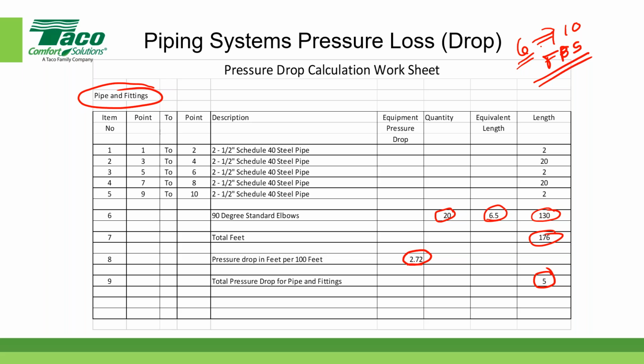Now, in our case, we said less than 8 feet per second. So the larger you make the pipe, the lower the velocity, and the more risk you have of collecting air and not moving the air along and removing it from the system. Does that help in that explanation? Yep. And Chris asked, please explain the importance of minimum velocity. I think you just covered that. Air is probably the biggest issue. We want air to move along with the water stream and then be taken out by the air and dirt separator.